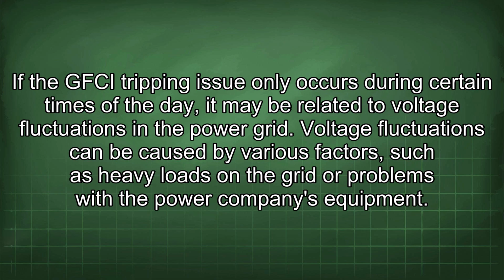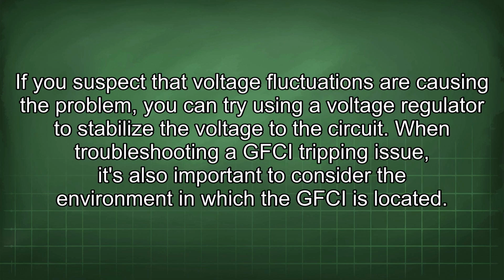If the GFCI tripping issue only occurs during certain times of the day, it may be related to voltage fluctuations in the power grid. Voltage fluctuations can be caused by various factors, such as heavy loads on the grid or problems with the power company's equipment.